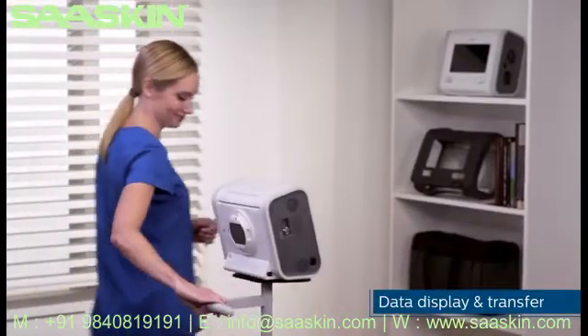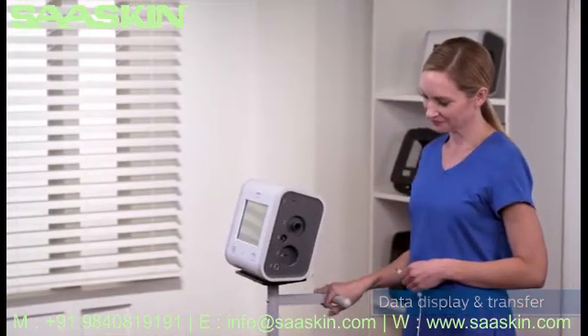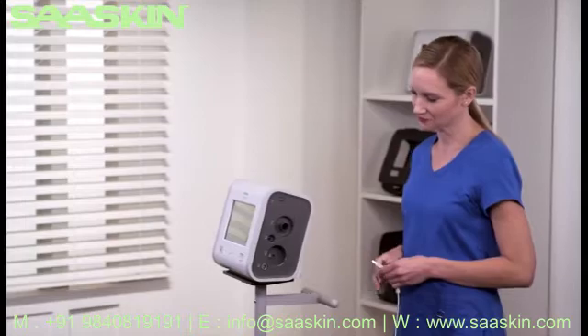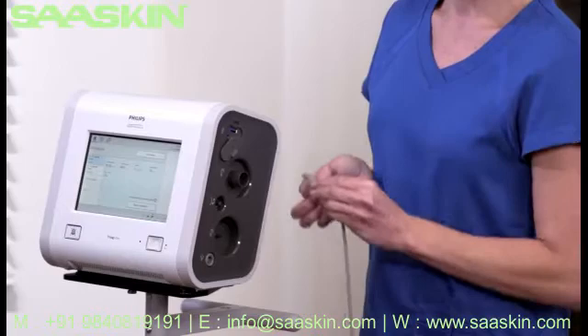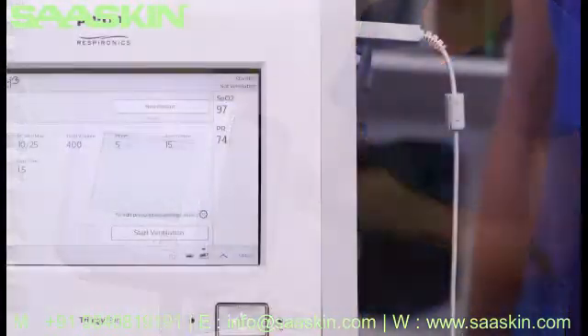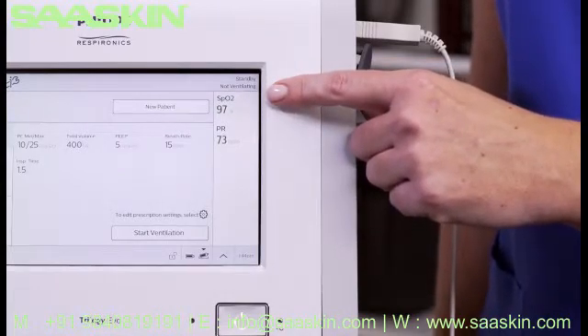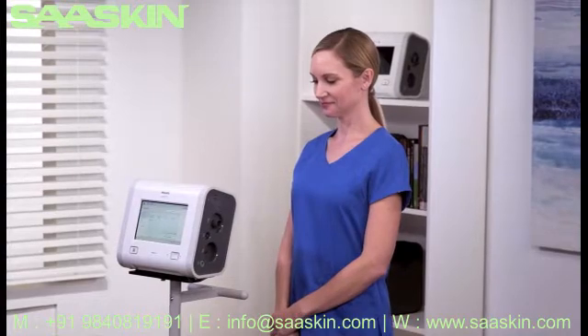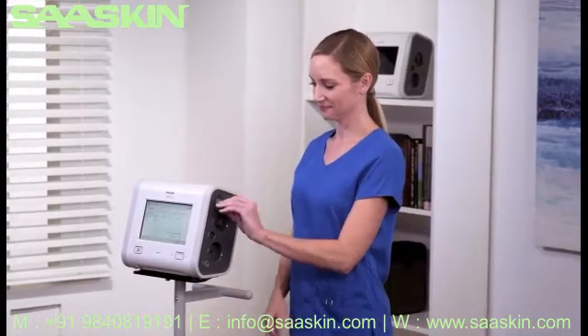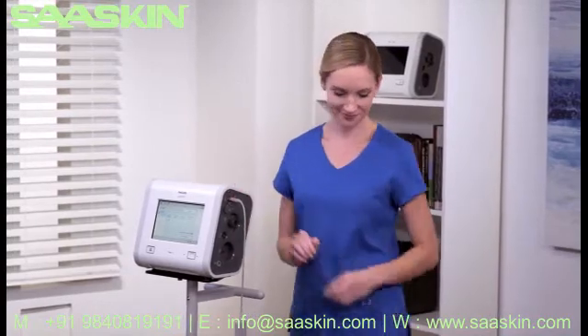Trilogy EVO offers several connection options for displaying and transferring data. We'll review the data display accessories: SpO2 and EtCO2. Insert the appropriate cable into the USB on either the patient or utility panels. You can see the SpO2 measurement in the monitor parameters pane and the pulse rate information in standby and various monitoring views. To check EtCO2 levels, insert the USB end of the cable into Trilogy EVO and attach the appropriate airway adapter on the other end.